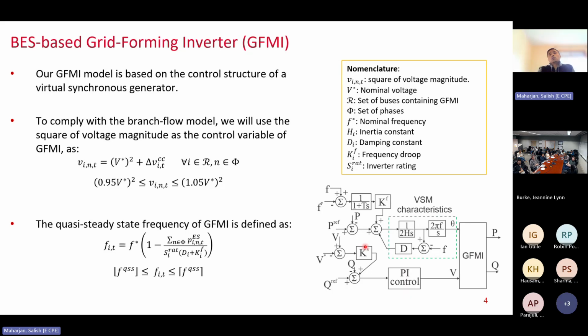Okay, but we want to look at the grid forming inverters from a different perspective, mostly from a load flow perspective, because we want to model the black start of the whole distribution system. So we want to model the grid forming inverters in terms of output voltage, output active and reactive power, and also in terms of output frequency. That's the objective. As I said, the grid forming inverter's output voltage can be regulated and the frequency can also be regulated, right? So we want to relate those voltages to active power or some parameters of the grid forming inverters, right?